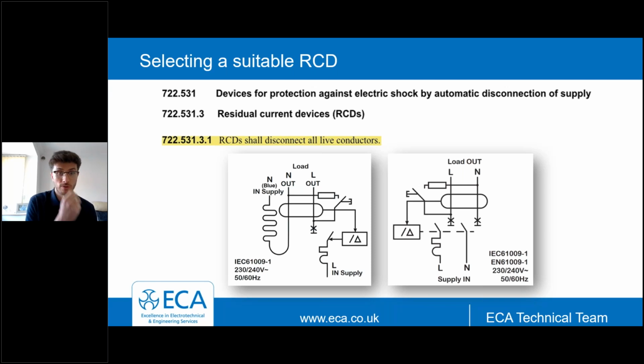So in order to fulfill compliance with this regulation, you need to ensure that your RCDs protecting the EV charge point equipment will disconnect all live conductors in the event, let's say, of a fault occurring. So we've got two images up on screen now. The image to the left shows what we call a single pole device. So you'll see that the neutral conductor is permanently linked on the supply side to the neutral conductor that would be connected on the outgoing side of the device. And then the switch conductor would purely be the line conductor, that would occur and make it a single pole device.